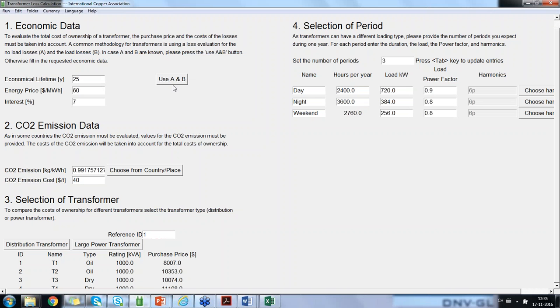In case they can be calculated within this tool. So in case you have a transformer and you don't know what your A and B factor will be, and the manufacturer is asking for it, and he will often do, because in his formula he will calculate the total price of the transformer, including the capex and opex. He will calculate it during the design, taking into account and make the sum of the purchase price, add A times the no load losses plus B times the load losses, and the lowest value from that formula is the one that he is using to give you the transformer with the optimized losses for your case.